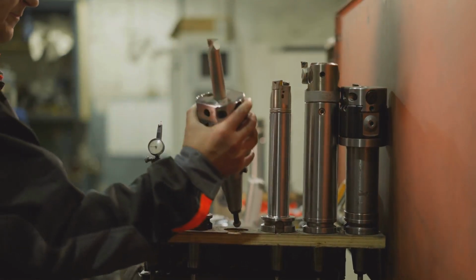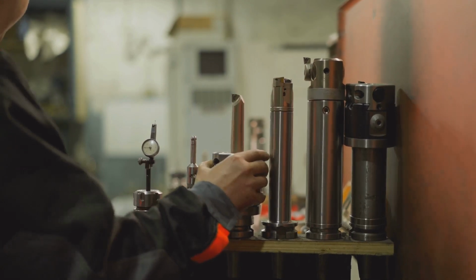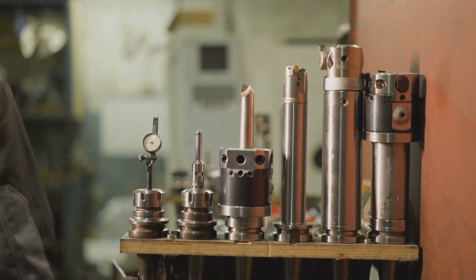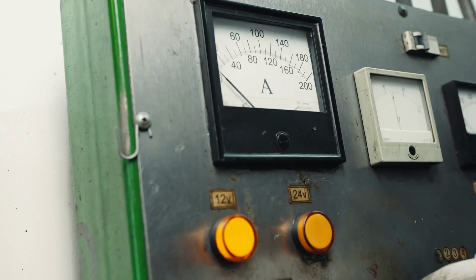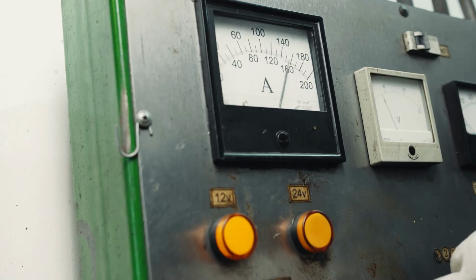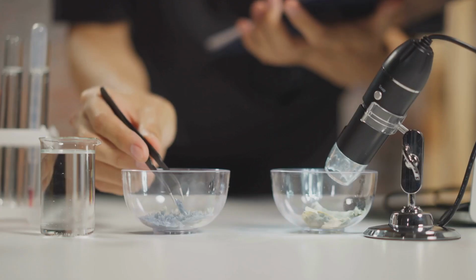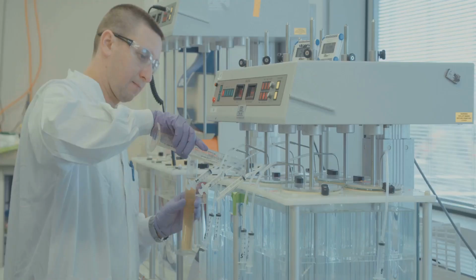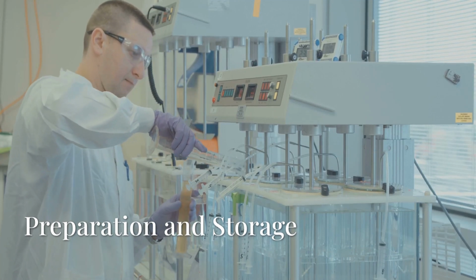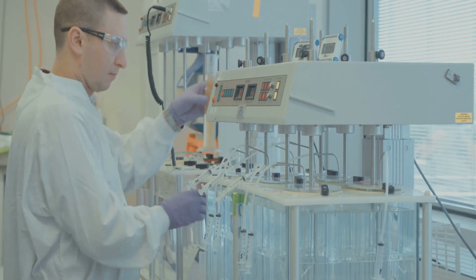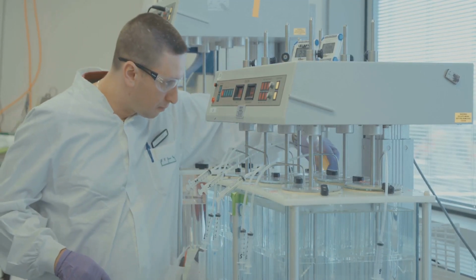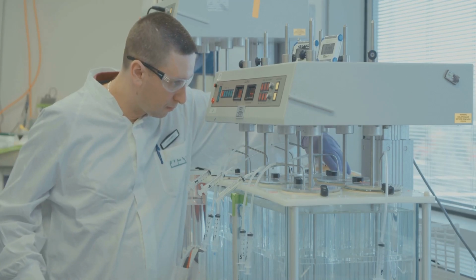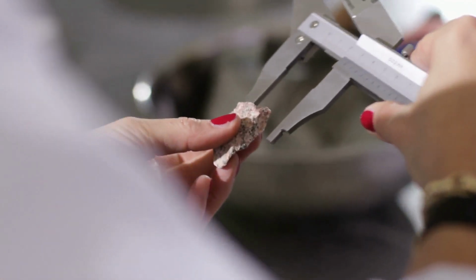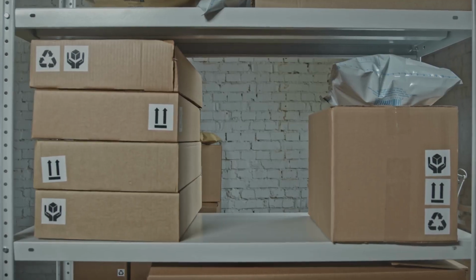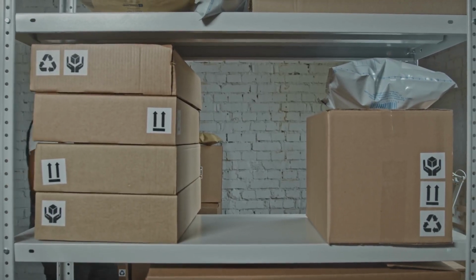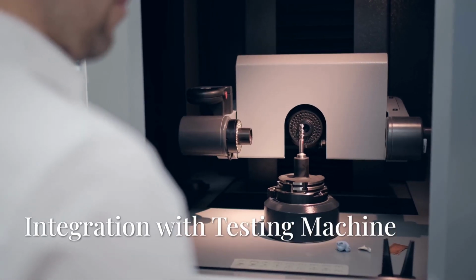It's also vital to determine how you will calibrate and verify the accuracy of your extensometer in advance. This can include electrical calibration, especially for strain-gauged extensometers, and visual inspection for displacement measurements. Additionally, it's important to plan for preparing and storing your extensometer for use. Many models actually come with protective coverings and cases to ensure that they remain in good condition when not in use.